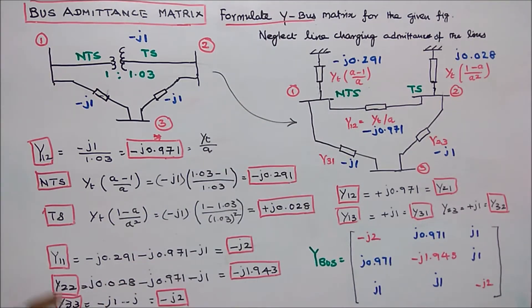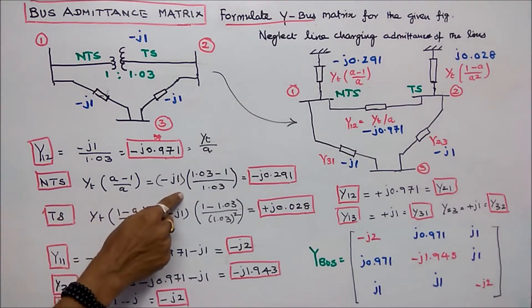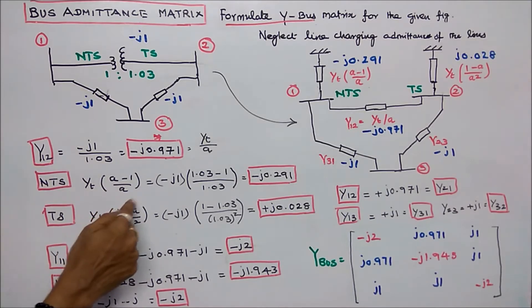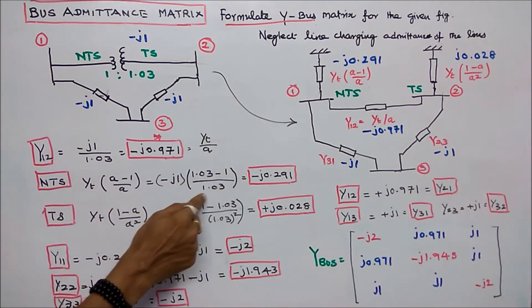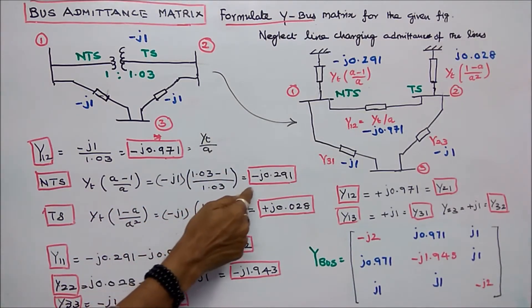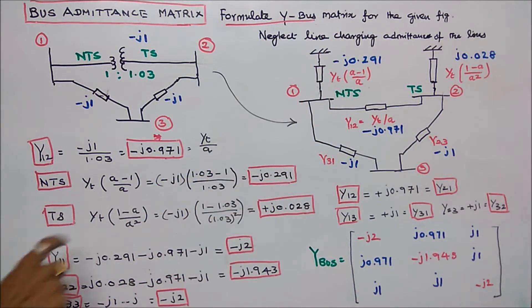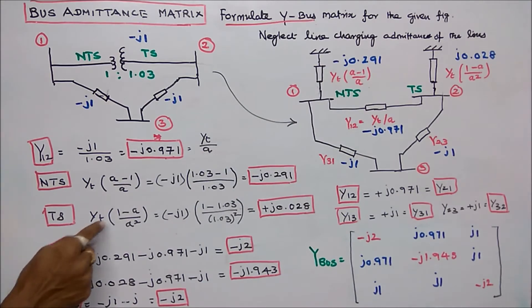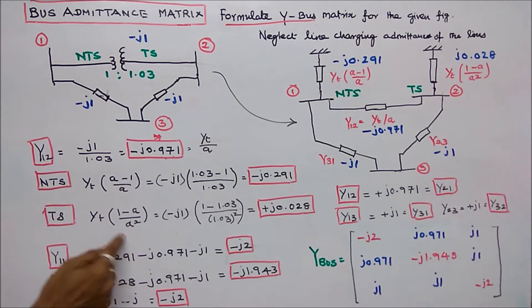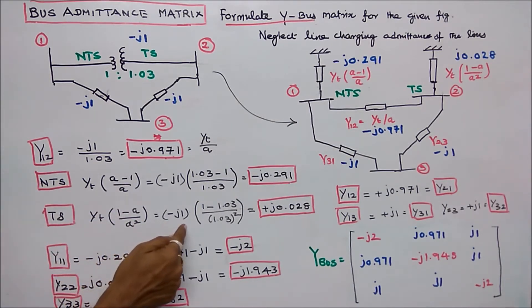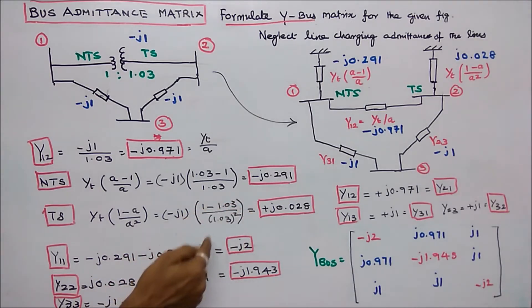The non-tap-setting side line charging admittance is Yt times (A minus 1) divided by A: minus J1 times (1.03 minus 1) divided by 1.03, which equals minus J0.0291. On the tap-setting side, Yt times (1 minus A) divided by A squared: minus J1 times (1 minus 1.03) divided by 1.03 squared, which equals J0.028.